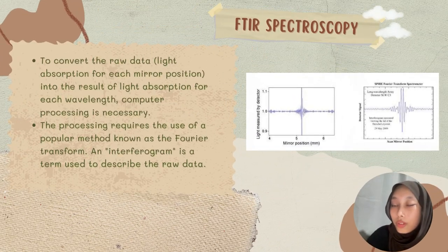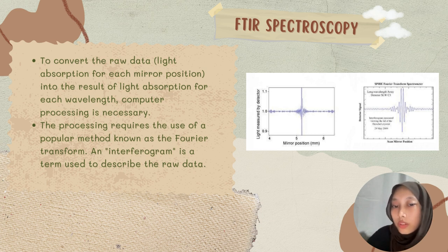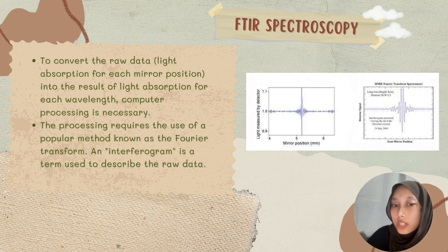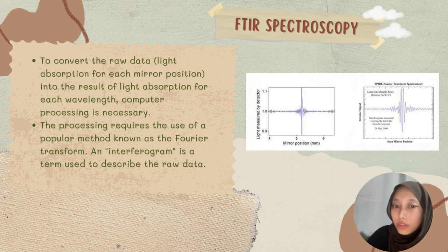Different wavelengths are modulated at different rates, so the beam coming out of the interferometer has a distinct spectrum at any given time. To convert the raw data — light absorption for each mirror position — into the result of light absorption for each wavelength, computer processing is necessary. This processing uses a popular method known as the Fourier transform; the raw data is referred to as an interferogram.